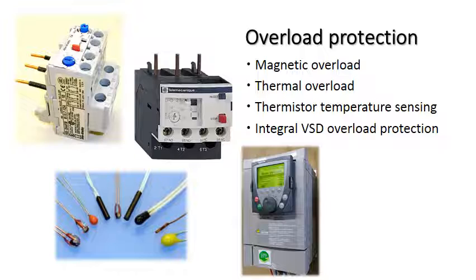Overload protection, it's pretty important, and there's four that we're going to discuss: magnetic overloads, thermal overloads, thermistors, which are temperature sensing, and of course the integral VSD overload protection. Did I say what VSD stands for? Variable speed drive.